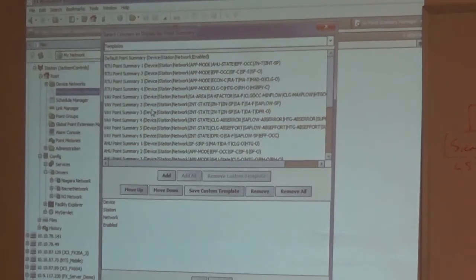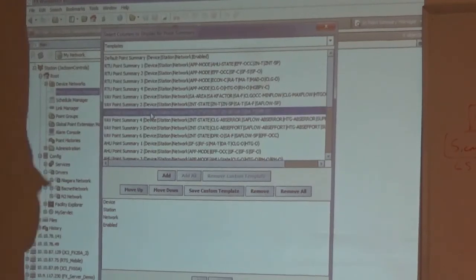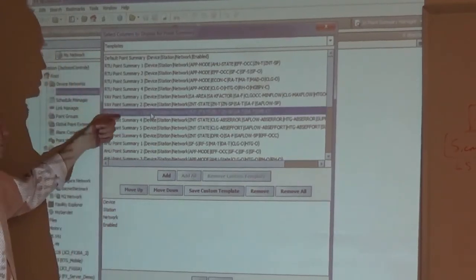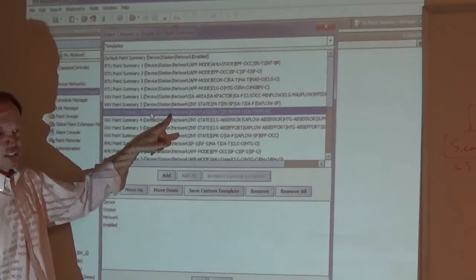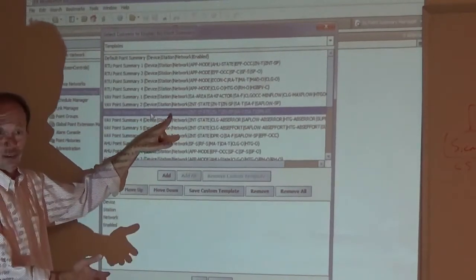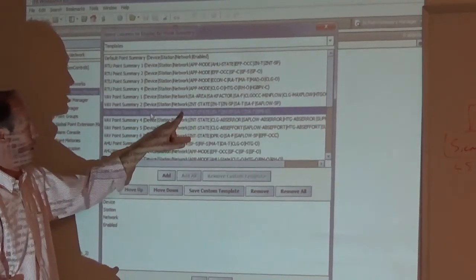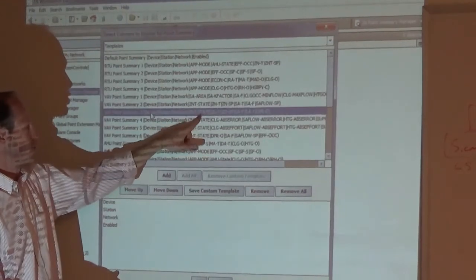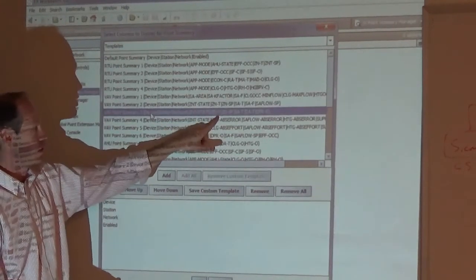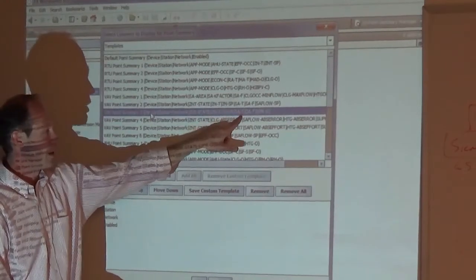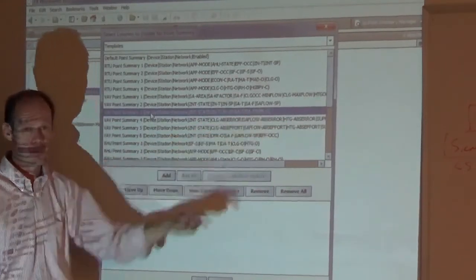Let's just take a look at this one. So it's going to show my VAV box, what network it's on, what station it's on, because you could have multiple stations if you're at a server level. It's going to show what network it's on, BACnet or N2. It's going to show my zone temperature state value, zone temperature set point, supply air temperature, discharge air temperature, and damper position for all the boxes.